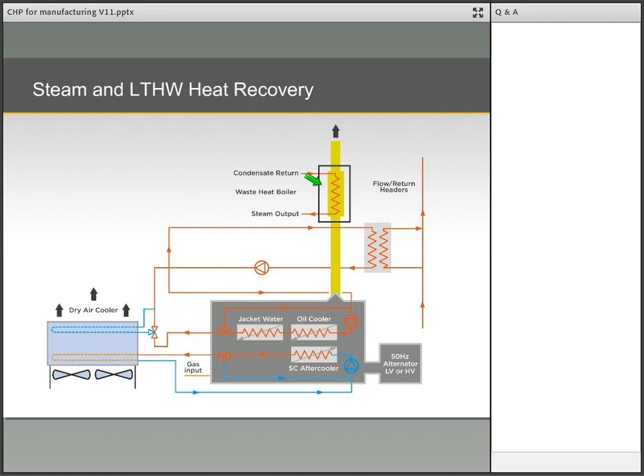For many sites, the use of all CHP heat can be a problem, especially in the summer months. However, if there is a chilled water requirement, the surplus heat can be used in an absorption chiller to produce chilled water. Absorption chillers use the low temperatures required to evaporate water under a vacuum to further chill already low temperature water, standard operating conditions being around 12 C return and 6 C flow temperatures. The water within the chiller is transported around a closed loop via a chemical, usually lithium bromide, and the heat from the CHP is used to separate the water from lithium bromide in the generation section of the chiller.